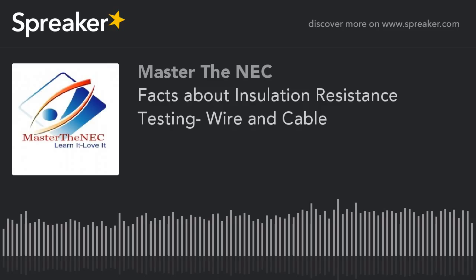All right. Yet these conductors have measured the insulation resistance at the factory, and it's acceptable. But then you get it out and you install it, and you get these varying readings. And you have to understand that the values that you're going to get in our facility or any of our manufacturers' facilities are nowhere near the values that you're going to get. Now, some people might say, well, they should be.